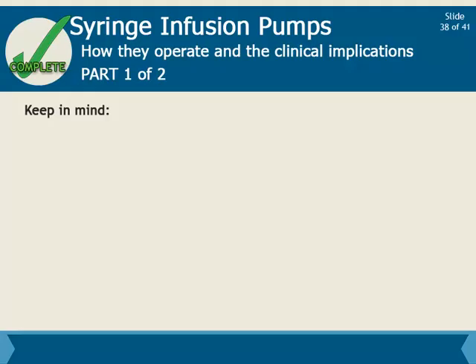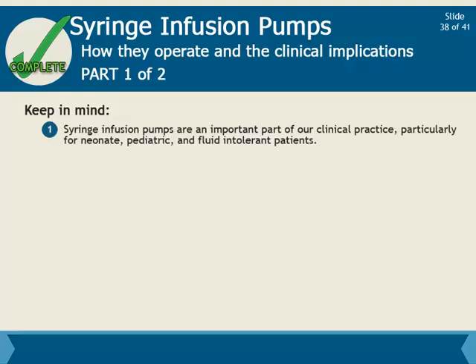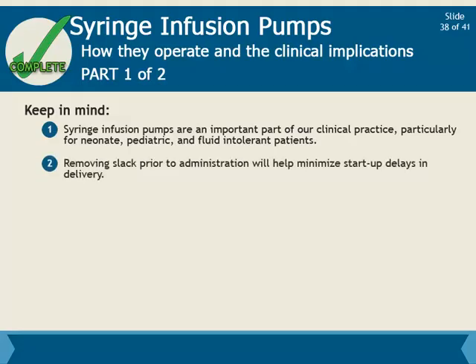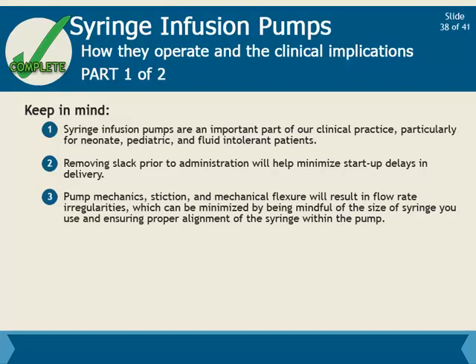The key things covered in this module to keep in mind as you continue to provide excellent care are: 1. Syringe infusion pumps are an important part of our clinical practice, particularly for neonate, pediatric, and fluid-intolerant patients. 2. Removing slack prior to administration will help minimize startup delays in delivery. And 3. Pump mechanics, stiction, and mechanical flexure will result in flow rate irregularities, which can be minimized by being mindful of the size of the syringe you use and ensuring proper alignment of the syringe within the pump.